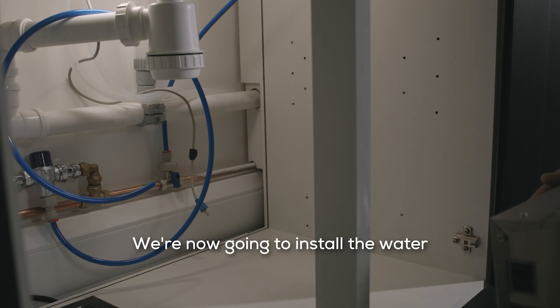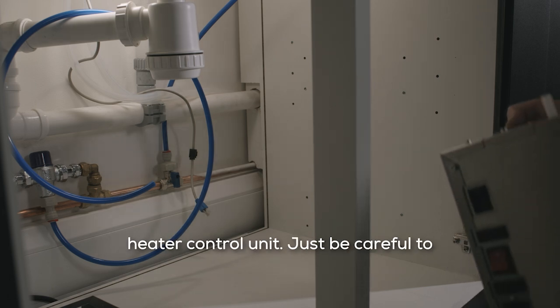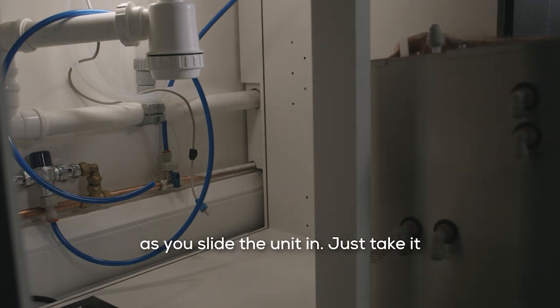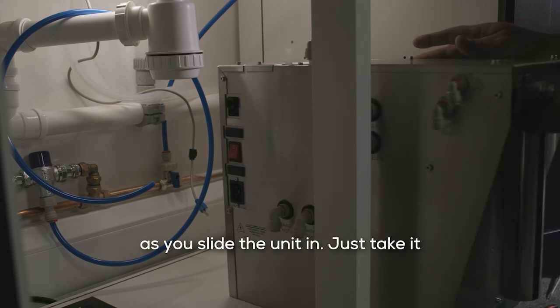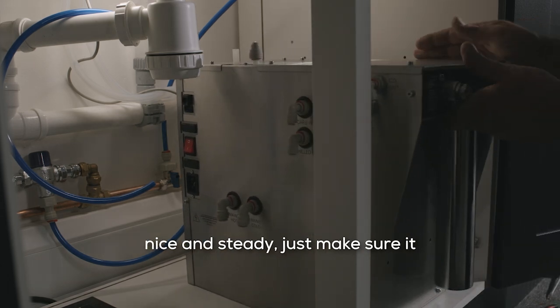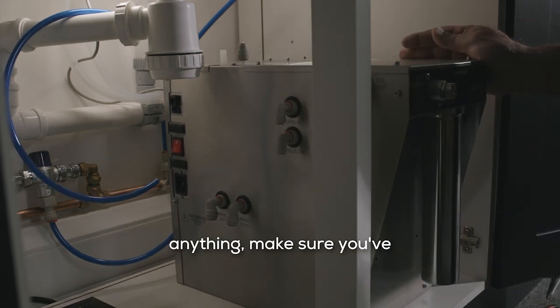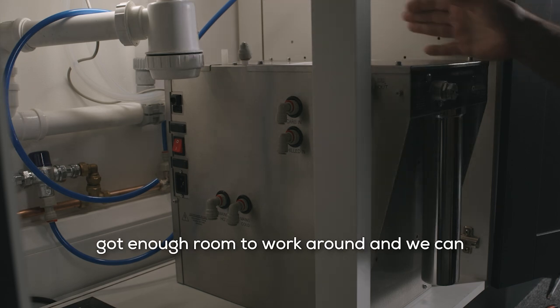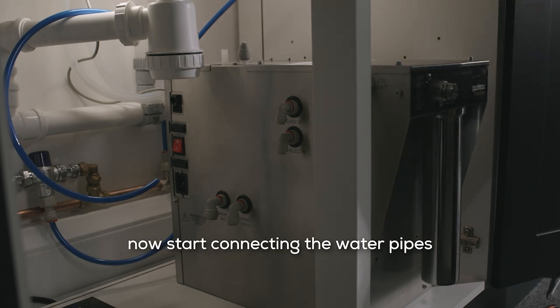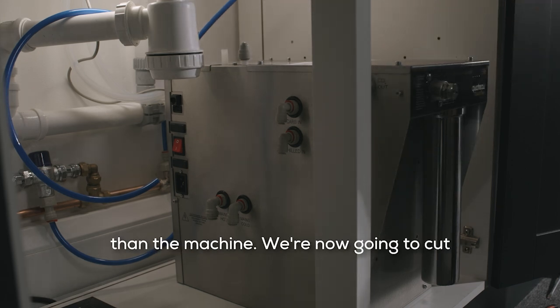We're now going to install the water heater control unit. Just be careful to make sure you don't damage the cupboard as you slide the unit in. Just take it nice and steady. Just make sure it doesn't foul on anything. Make sure you've got enough room to work around. And we can now start connecting the water pipes to the machine.